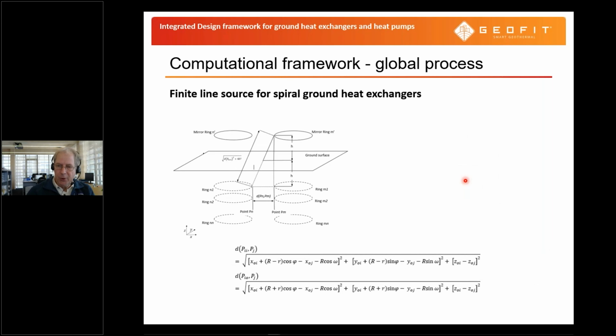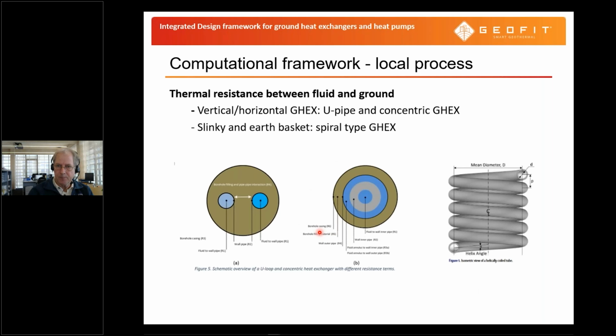For the earth baskets, what we did is that we took the ring type heat exchanger and we said, okay, we can use this as a kind of stack, a layer of pancakes in the soil, and then we have another stack at a certain distance, also a layer of pancakes in the soil. And in this way, we can calculate the effect of an earth basket heat exchanger. So again, exactly the same type of solution, only extended to 3 dimensions.